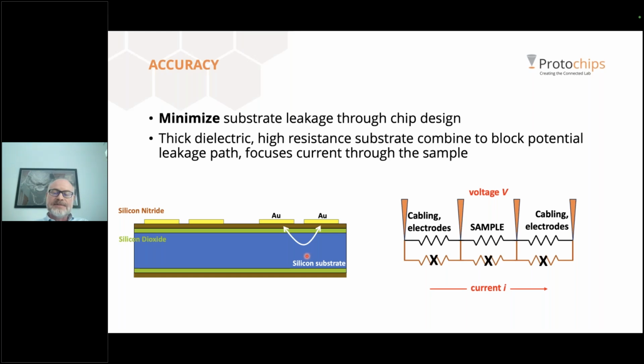All of our electrical chips are made using a special substrate with 2 features: very thick silicon dioxide films under the silicon nitride top layer and a high resistivity silicon substrate. These layers don't add to the membrane thickness, so you can still do high resolution imaging, but they are found beneath the pads, the electrodes on the chip, and importantly, they prevent any significant leakage current flowing around the sample through the substrate. So with our system, single picoamp measurements are not only possible, but typical. These features also improve the AC characteristics of the chip during switching by reducing parasitics.